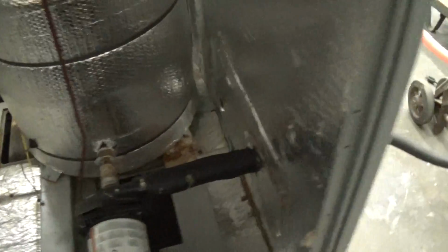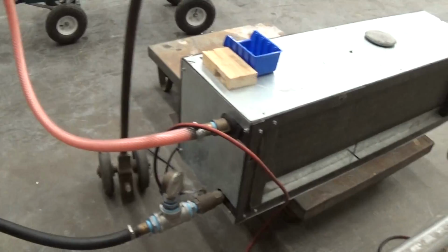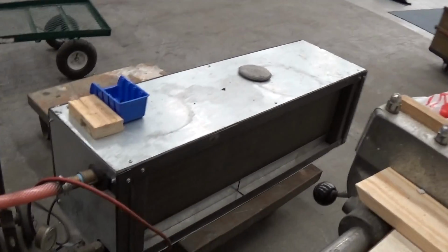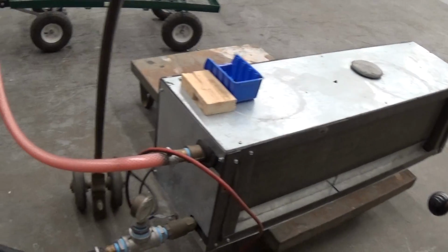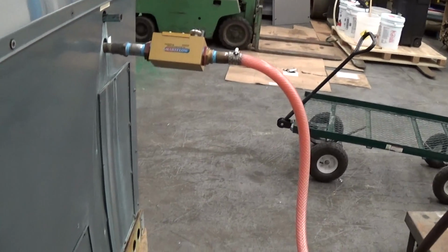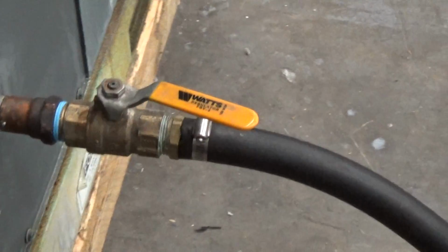What we usually do for a load on smaller units like this is we just run it through an air handler, which we had here. The air handler was basically used to heat the fluid up in this case. And in this case here, we got the ball valve here tweaked a little bit, and then the one on the air handler also about halfway. So right now, just to give you an idea, we're a little bit above 40 psi. And let me walk around here. And we got it adjusted.